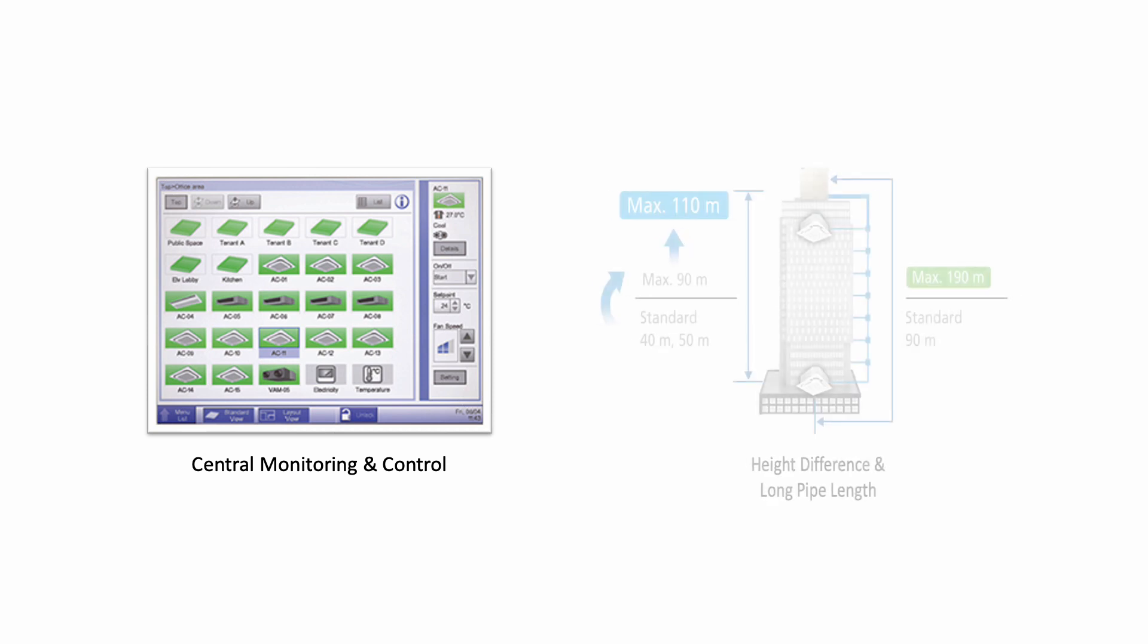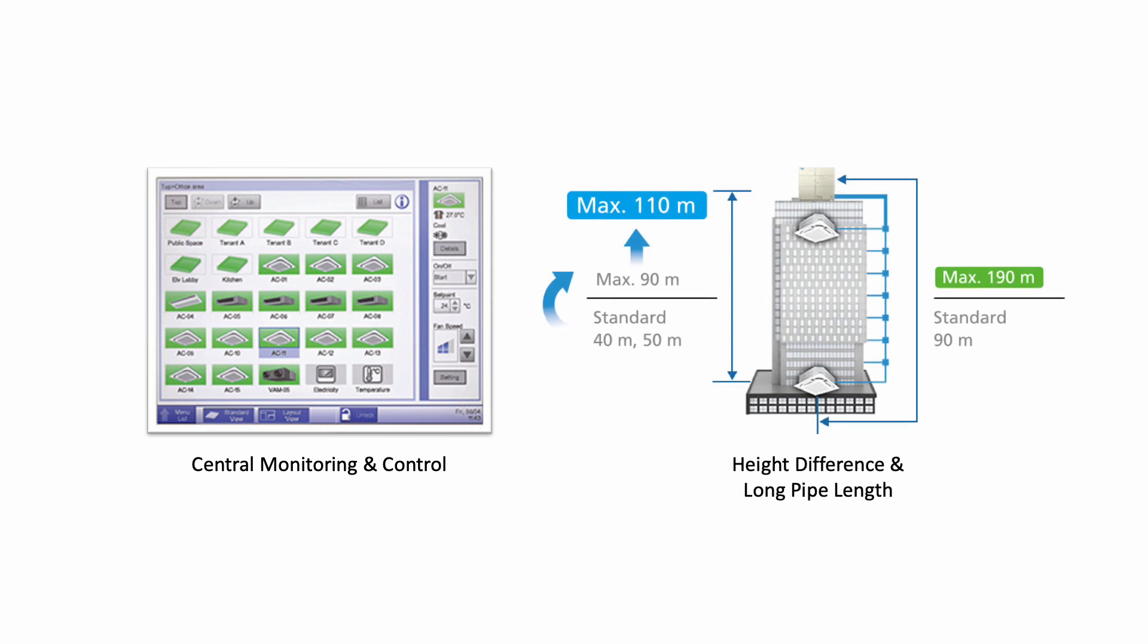The second reason you want to use VRF is because you have this vertical height limitation. You see, multi-split usually just maximum is about two floors. The distance between the indoor unit and the outdoor unit. If beyond that, then you have to use VRF system. If the capacity allows, and other things allow you, then VRF system is a very good choice.